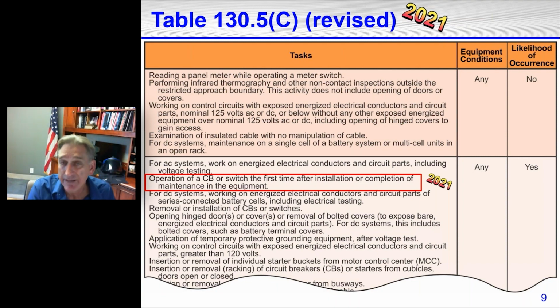And this could just even be a circuit, one circuit, single pole, double pole, or three pole breaker. What this is saying is first time you turn that on after it's installed, you look over on the right, likelihood of occurrence, yes. Well, what does that mean? That means there is a likelihood that something could happen. So at that point, you do have to wear arc rated PPE just to turn it on.